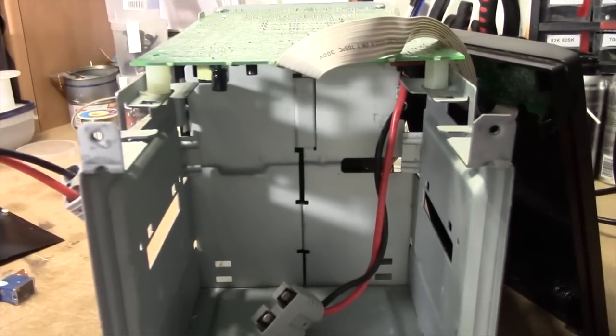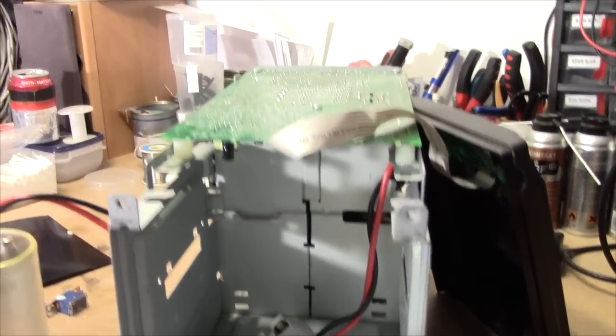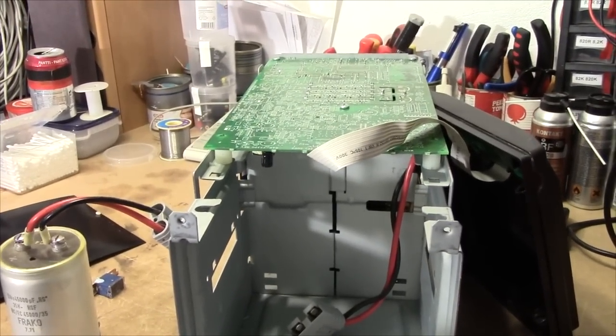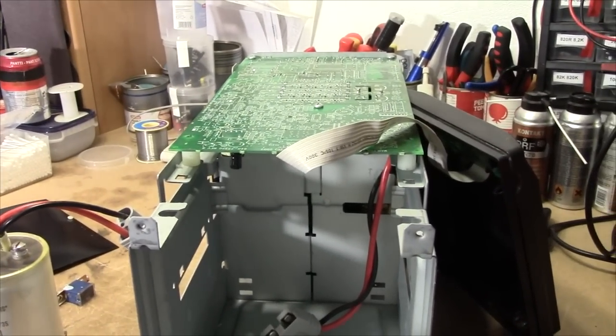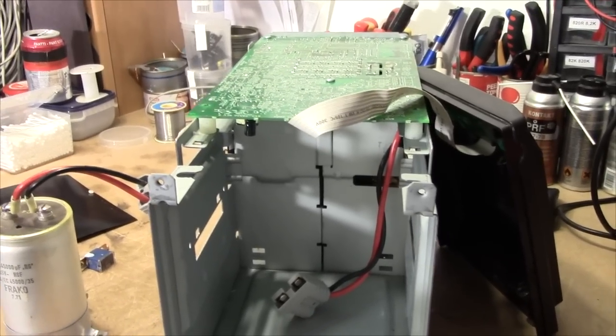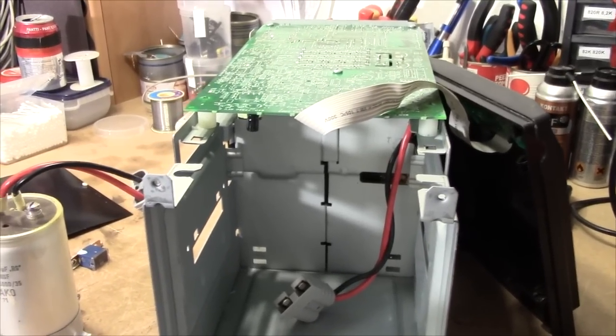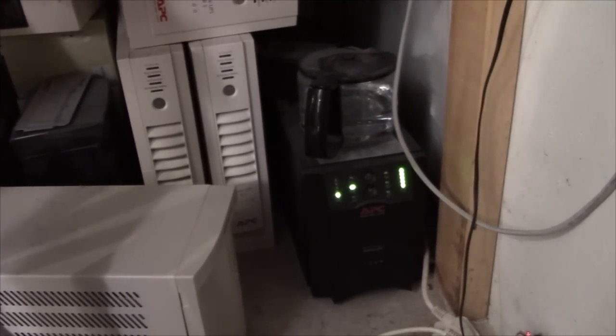But thanks to how these units are constructed, you can just hook up a serial cable and throw in a couple of commands to reconfigure the ADC calibration in order to lower the charging voltage, since it's a software controlled charger. And you can bring the voltage down to, well, very low usually. In my home UPS down there, which is hooked up to a couple of calcium car batteries, I've got it set to 13.1 volts per battery, and it's doing that just fine. And those batteries have lasted me since 2009 or so, and they show no signs of aging. I do top them up every now and again.